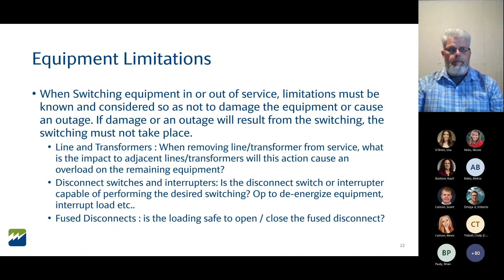If you're told to decouple, or open and lock and tag a motor operated disconnect, do I know how to do it? If my equipment is good and in service, do I know how to operate it? Does it look like it has the right pressures? That's where the pre-switching inspection comes in. When you get called to a station for switching, whether routine or emergency, go take a look at that equipment and the substation, make sure things are free of hazards, and make sure you understand how to operate it properly before you go through the switching process. That's the pre-switching inspection, and it's very important to successfully switching equipment.